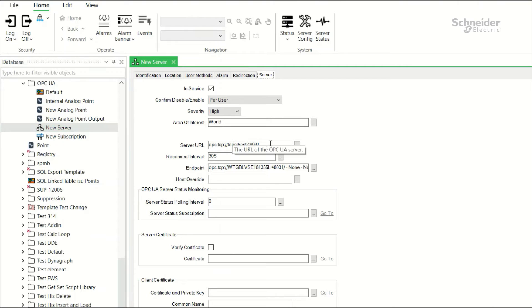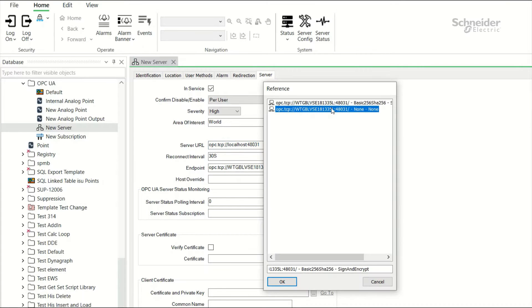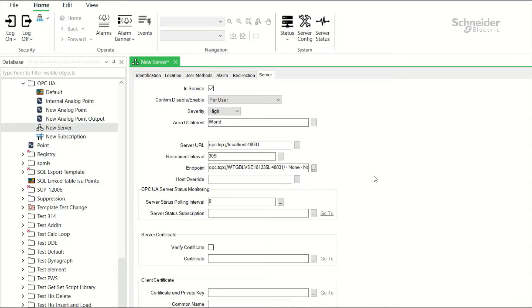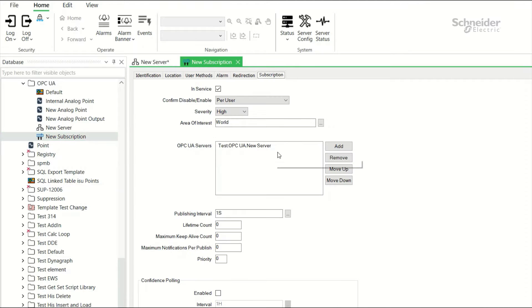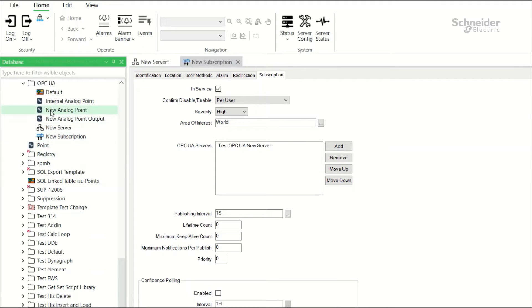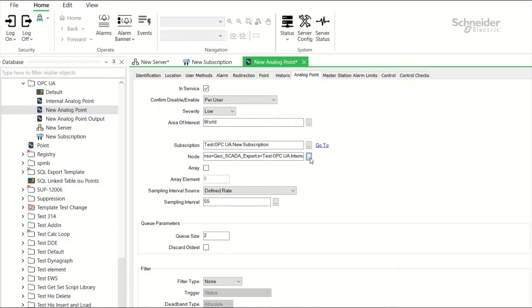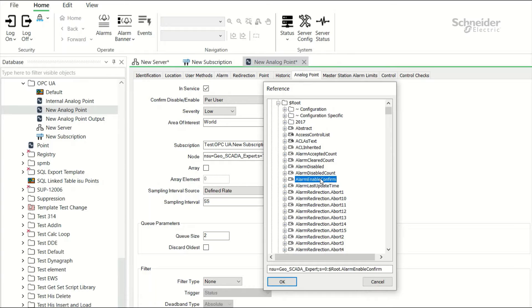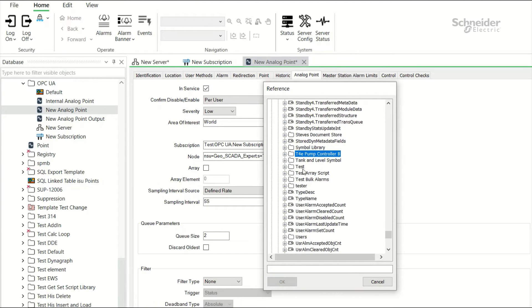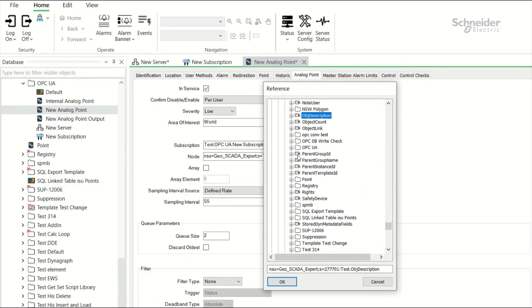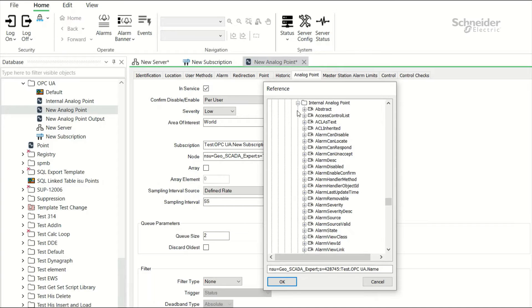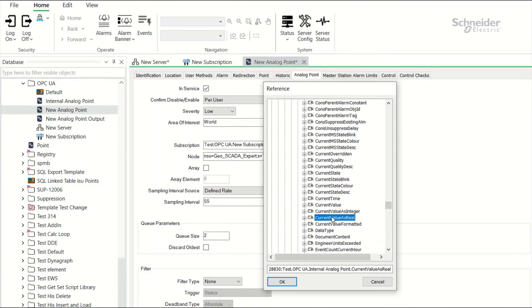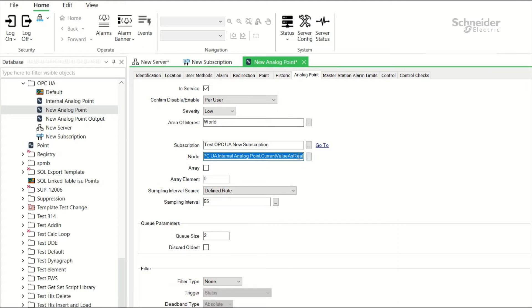You may also wish to disable encryption for trials until you set up certificate-based security later. Here's an example sequence showing the items needed to set up Geoscada to read a point's value from another system. Create and select a server and add a host name and port — the letters OPC.TCP and punctuation here are important. Select the endpoint, either unencrypted or encrypted, and further down see the certificate and credential fields you might need. You'll need a subscription to set scanning parameters and then a point linked to that subscription. Use the browse feature on the point to find the tags needed, in this case from the Geoscada OPC UA server in Geoscada 2023.